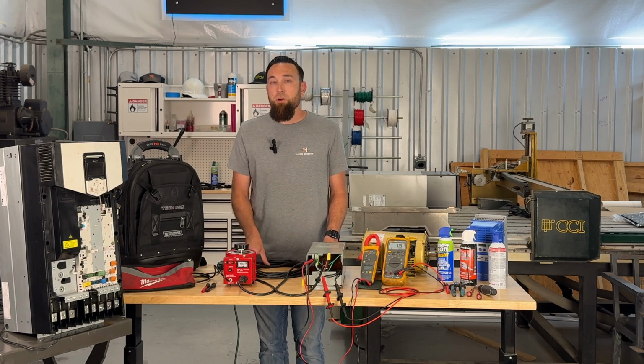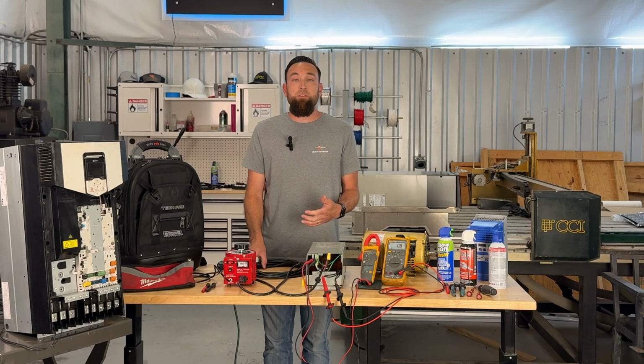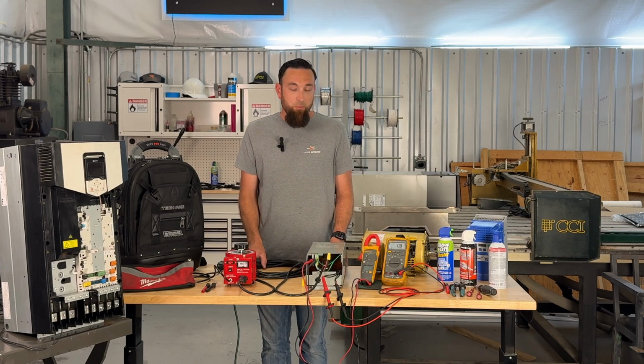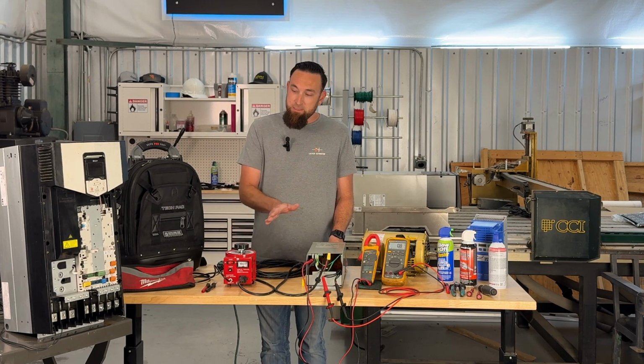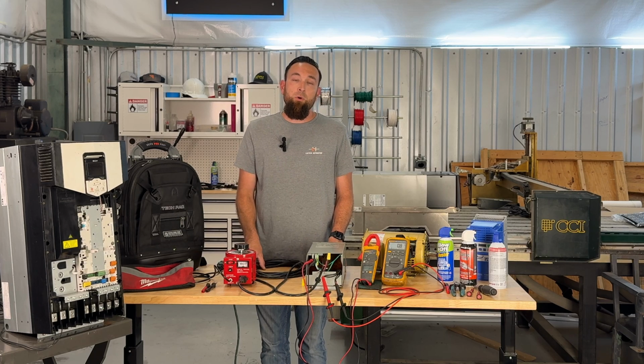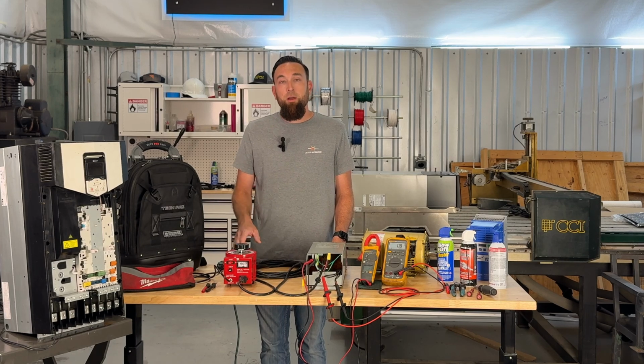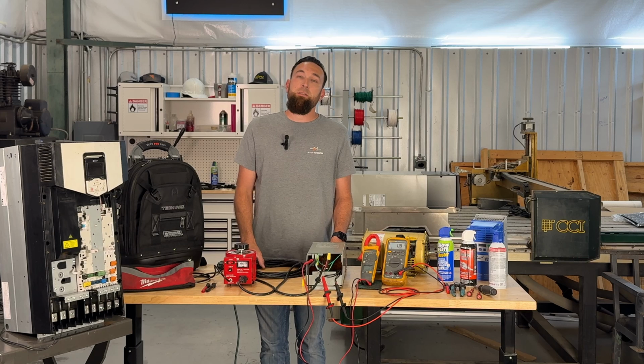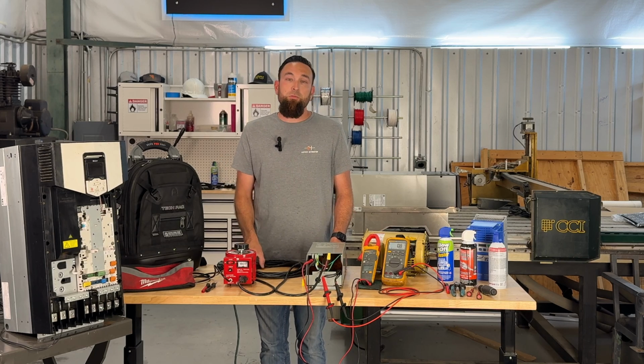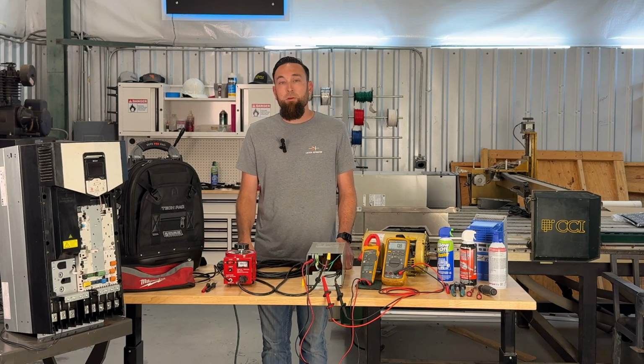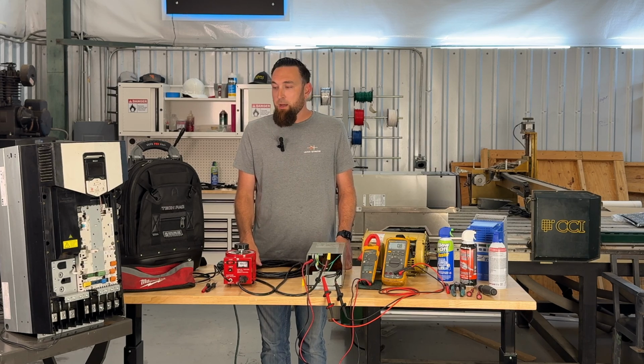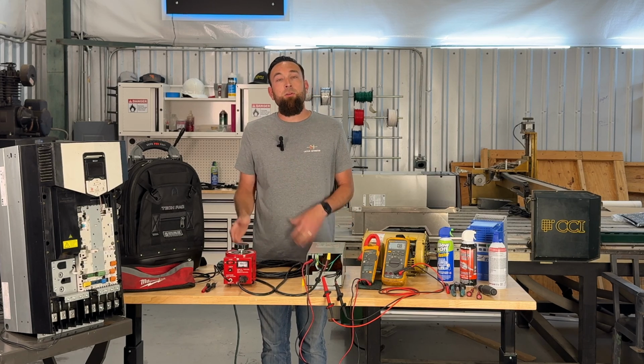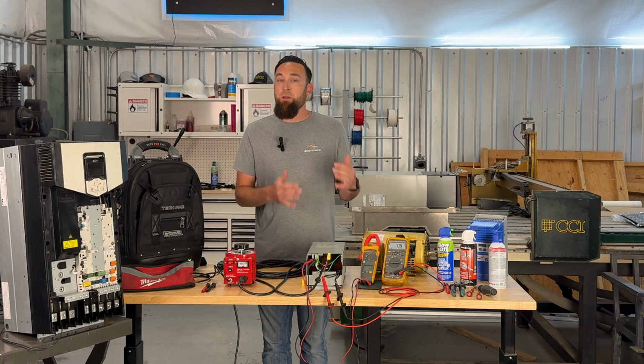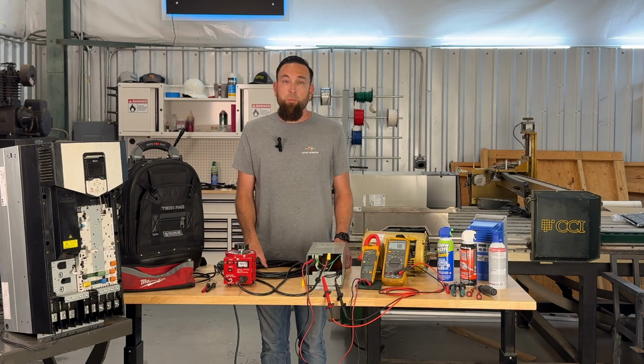On a 460 volt drive, our standard is to do 50 volts an hour. Same process, put 50 volts AC on the input on line 1 and 2 on this particular drive. We let it sit there at 50 volts for an hour, raise it up to 100 volts, let it sit there for an hour, all the way up until we get to 460 or 230, whatever your rated voltage is. That needs to sit there for an hour, and then you can switch over to your normal three-phase line voltage and just throw the power to it.